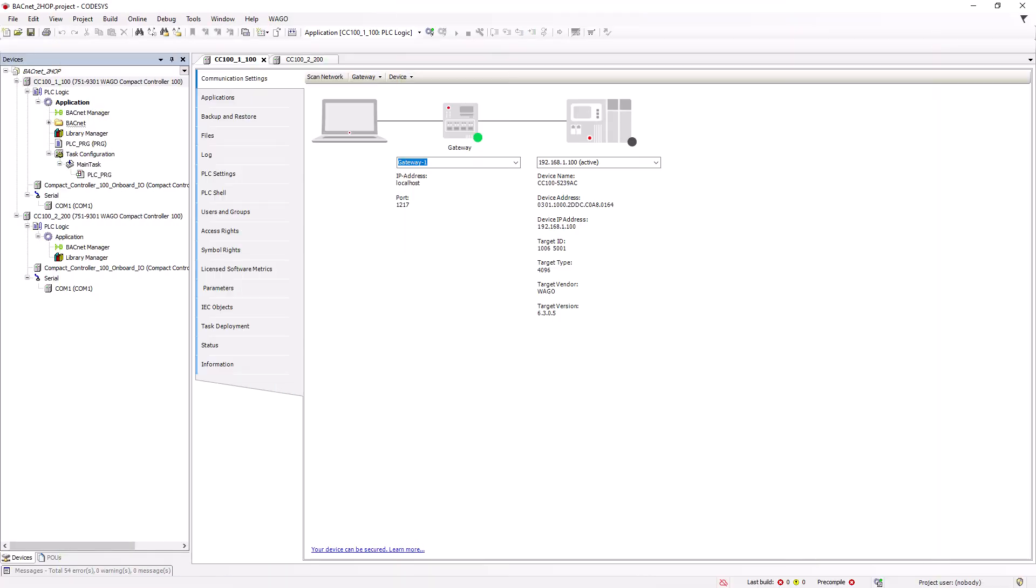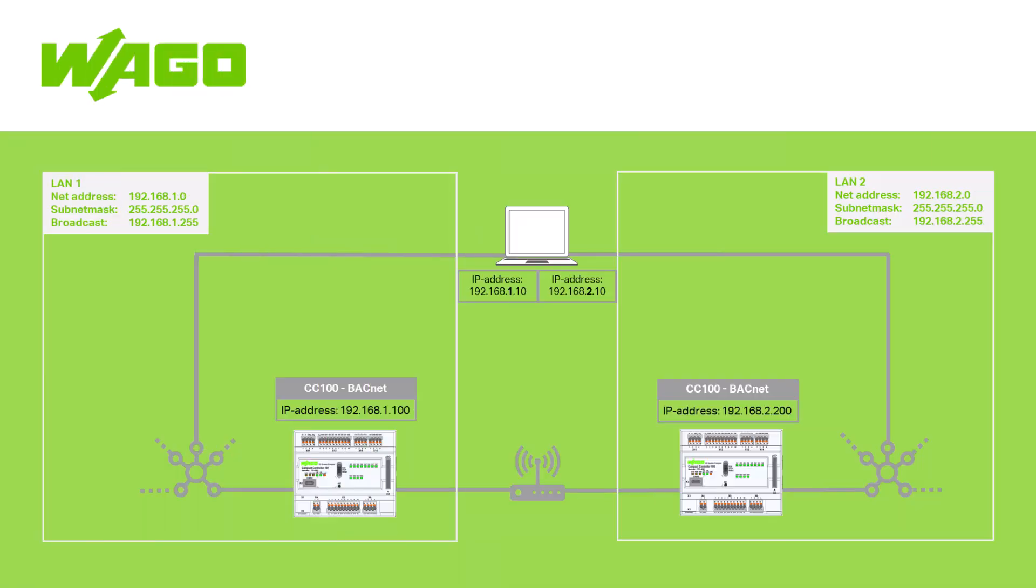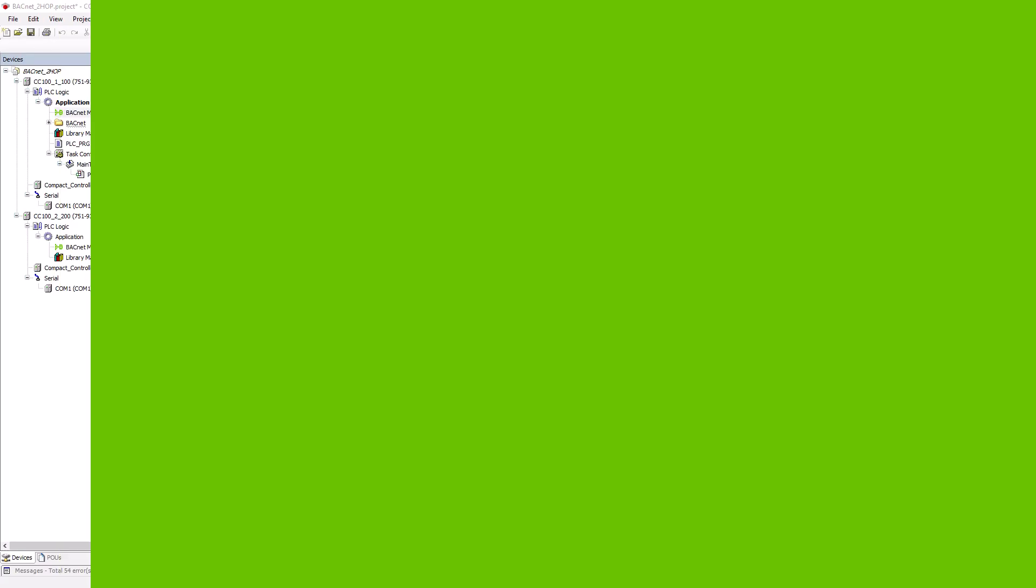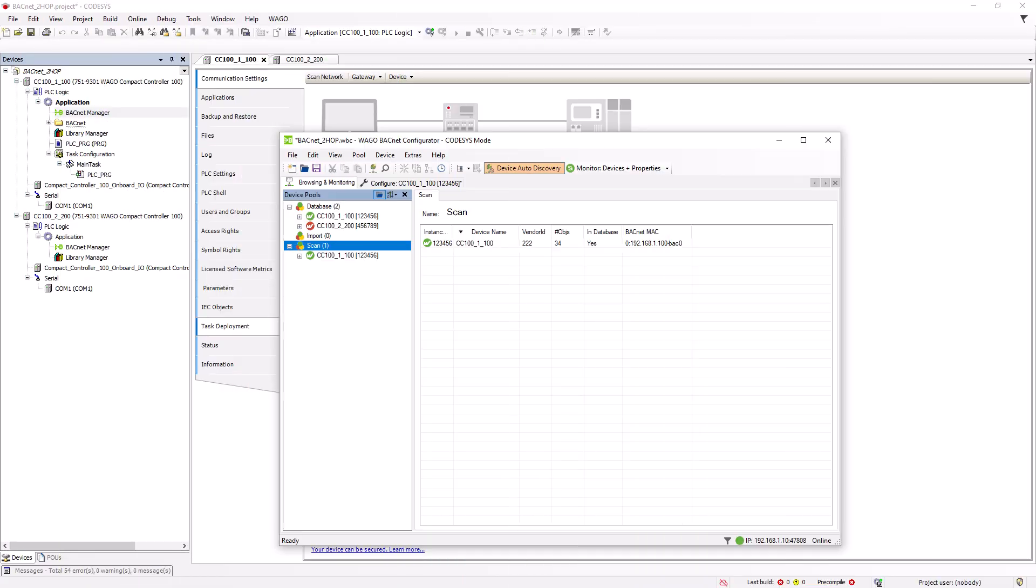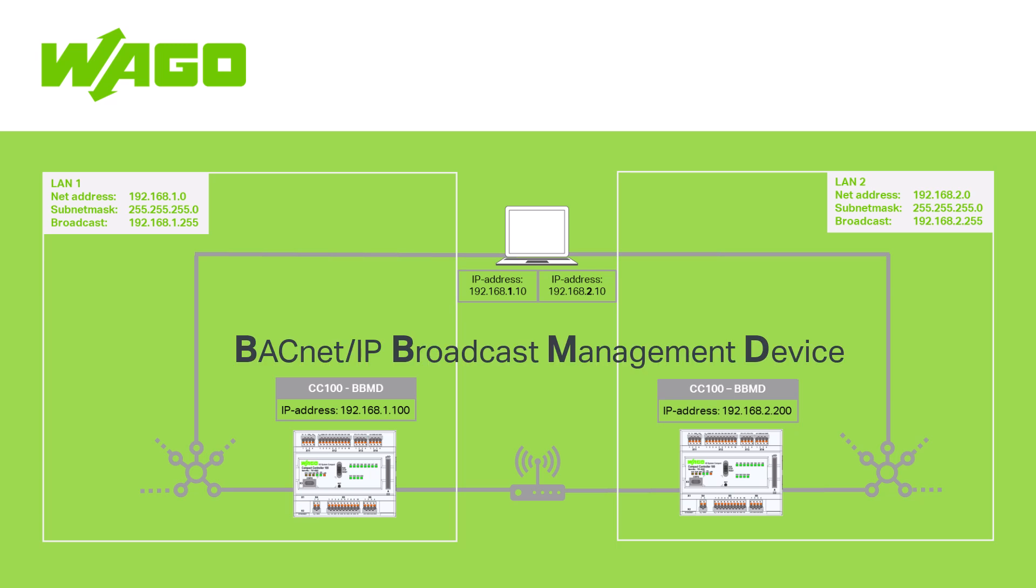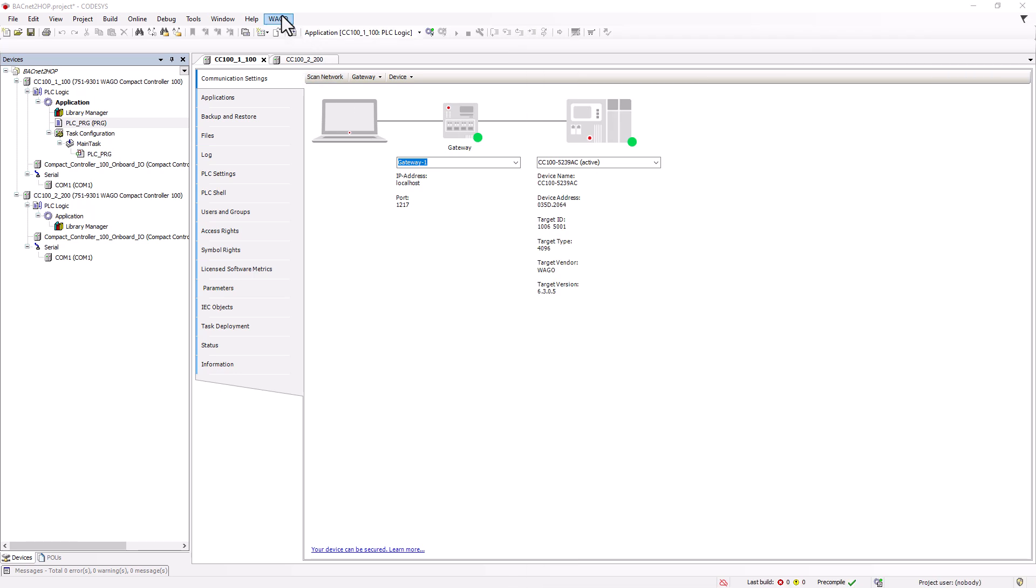We have created both controllers in a Codesys project and we can dial into both subnets via two Ethernet interfaces and the subnet's own controller is recognized as an active BACnet participant in the BACnet configurator. What is not yet possible is to find the other controller beyond the boundaries of the respective network. To do this, we need to configure both controllers as BBMD and create a broadcast distribution table for each.